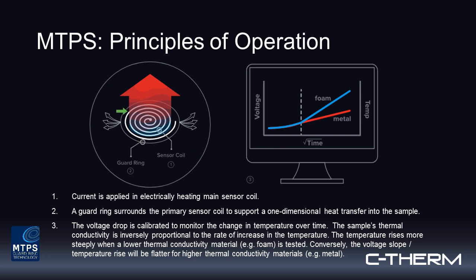Your guard ring on the outside is another very important aspect of the sensor chip, which allows for a one-dimensional heat transfer into the sample. The benefit that offers is your sample only needs to cover 17.8 millimeters in diameter for solids, and you need a very small volume when you're measuring liquids or powders.